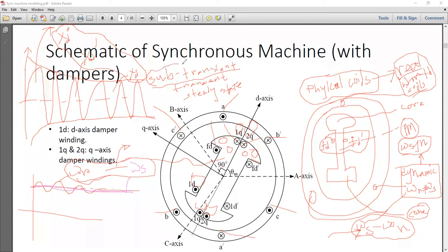We are treating them as different periods. So actually to model these phenomena, subtransient dynamics, transient dynamics, and steady state dynamics, we generally use this fictitious representation of damper coils. Okay, this is the final answer. We actually model, even if there are no physical coils, some modeled effect of these things: subtransient effect, transient effect, and steady state effect. Okay, and that's why actually these numbers might vary.